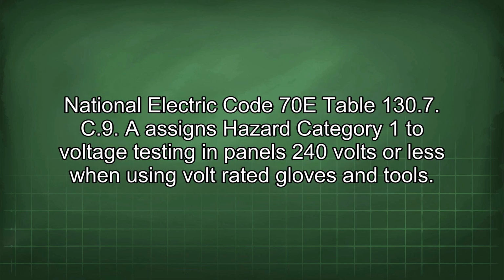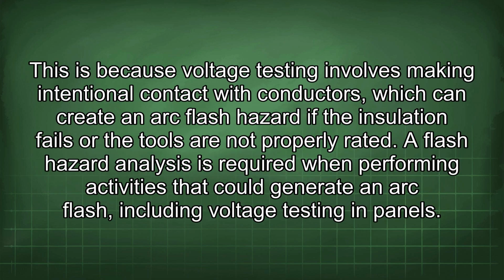National Electric Code 70E Table 130.7 C9 assigns hazard category 1 to voltage testing in panels 240 volts or less when using volt-rated gloves and tools. This is because voltage testing involves making intentional contact with conductors, which can create an arc flash hazard if the insulation fails or the tools are not properly rated.